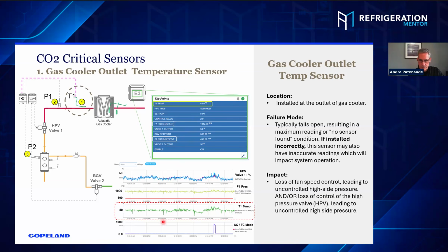If you don't, this is where you're missing the point, and you've got to understand this and look at it closely. Absolutely. If you are having a problem and you're trying to figure out what it is, graph it, and you've got one on top of the other, so you can see what's going on with the T1 temperature sensor, its pressure, the valve percent opening, all of that stacked one on top of the other. So it is a troubleshooting tool when you look at that, for sure.